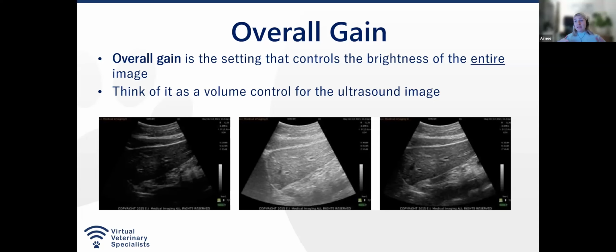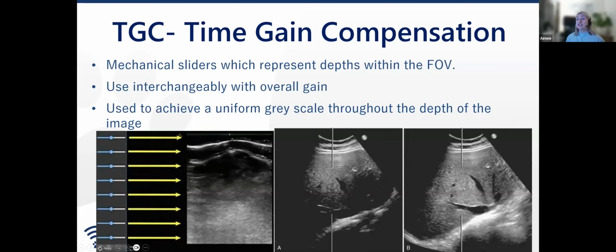So some machines will go from 0 to 100 for the overall gain. Some will go from 0 to 255, which is the sonoscapes for some reason. A rule of thumb is you want that overall gain set about 2/3 to 3/4 of the maximum. Okay, so on your machine, just turn the overall gain right the way down to the bottom, see what the number is, turn it right the way to the top, see what the highest is, and aim for about 2/3 to 3/4 of what that overall is. So the next function that you can use in conjunction with the overall gain, which, like I said, amplifies the returning echoes to the probe throughout the depth of the image.